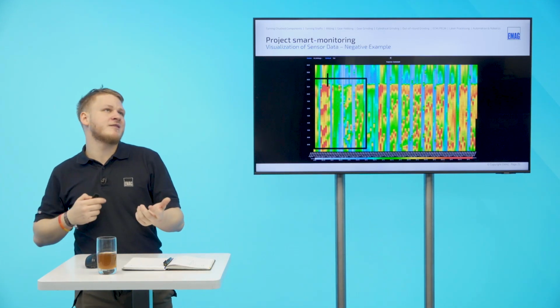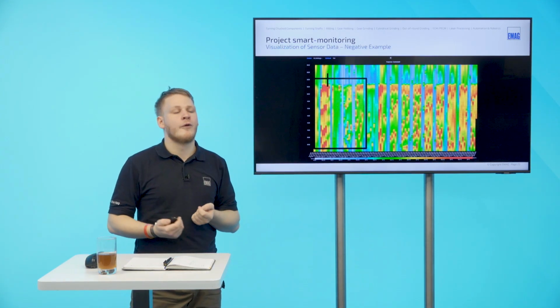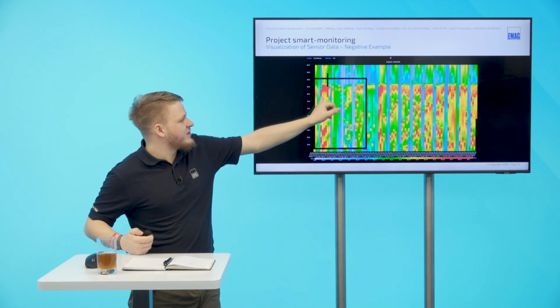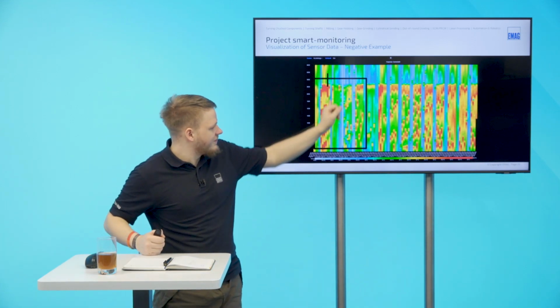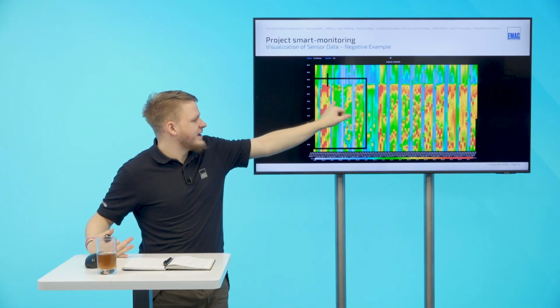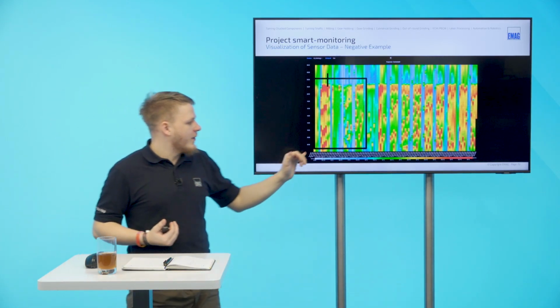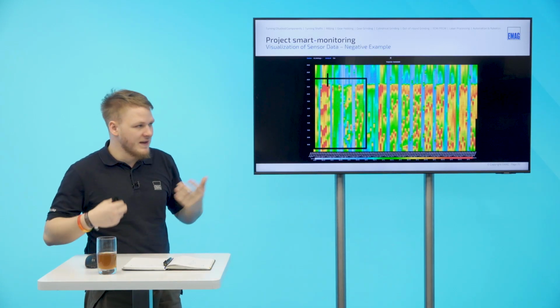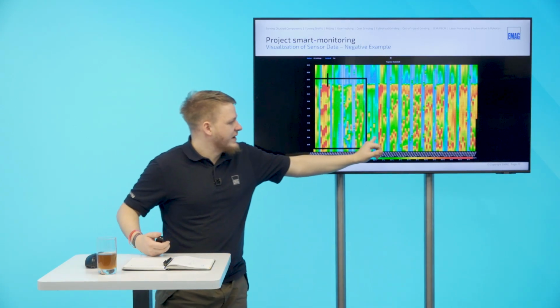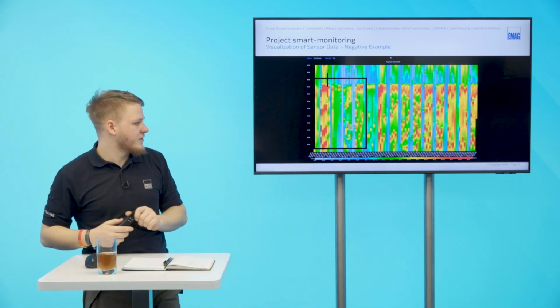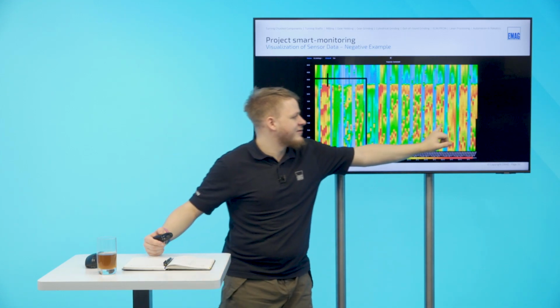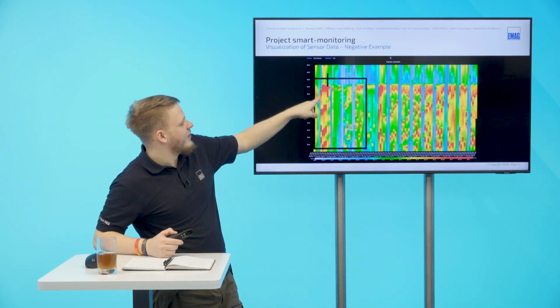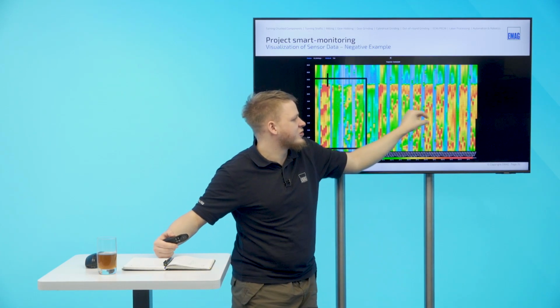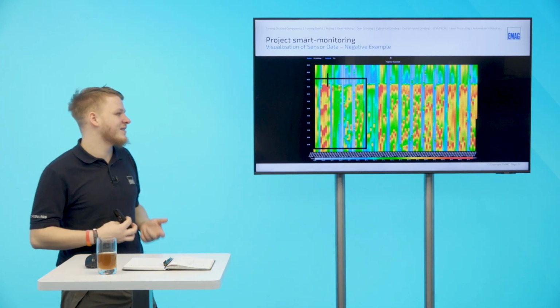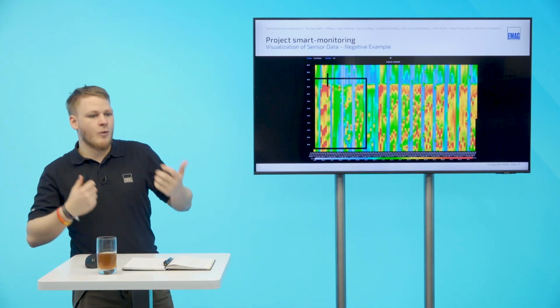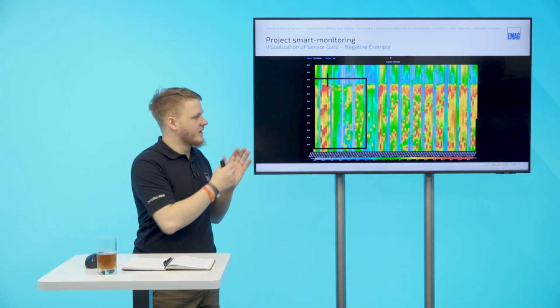If you see 1 degree is 3 to 6% more gas usage, that is nearly 3 to 4 degrees that we saved. Because we saw those data, we decided, okay, let's lower the heating point. We did that in the second week and went to the nice green range, which was acceptable for us. However, in the next week, we had a fault in the system where only one heater was running. After that, we decided to increase the target temperature of the factory floor to a 21 degree range, which is why it's a bit red again. But we don't have those long red blocks anymore. We just have it in really short times, which means the system is now performing as expected. And that was one of the points where we found waste of energy and simply optimized our setup.